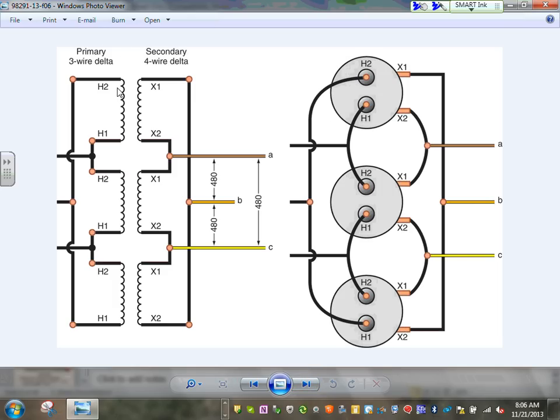Very easy. When I teach electricians how to wire, I always say that to get a delta, all you have to do is take all the coils and put them in series. Can you guys see that? Look at this. Here's one coil, two coils, three coils. Put them in series like this, all of them, and between every two coils, bring a phase. You've got yourself a delta. That's as simple as this.